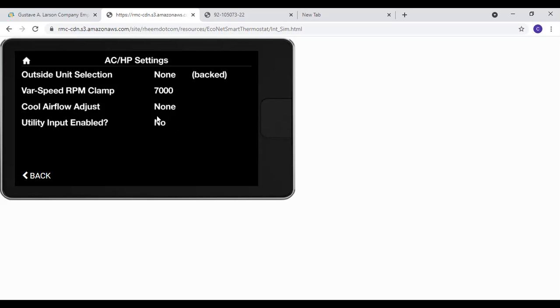Now, normally, if this is set up and actually a communicating system, this outdoor unit selection here would say EcoNet, and it would say locked, which allows you to basically lock it. It can't change what it is. And then this variable speed RPM clamp right here, 7,000, that's the maximum RPMs that you can run. That can be toned down, highlighted, and adjusted down from 7,000 if customers complain about excessive noise. They'll sometimes get those on the hottest of days or the coldest of days, where it's at the highest RPMs or in overdrive, is where you'll usually get your noise complaints.